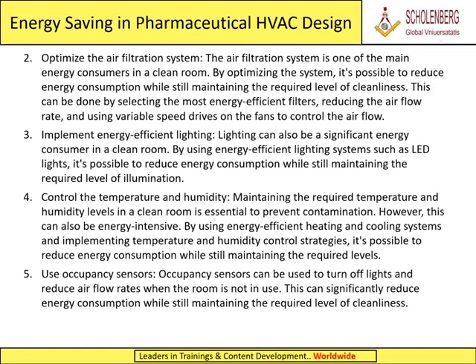2. Optimize the air filtration system. The air filtration system is one of the main energy consumers in a clean room. By optimizing the system, it's possible to reduce energy consumption while still maintaining the required level of cleanliness. This can be done by selecting the most energy-efficient filters, reducing the airflow rate, and using variable speed drives on the fans to control the airflow.